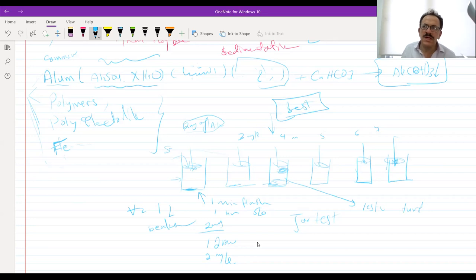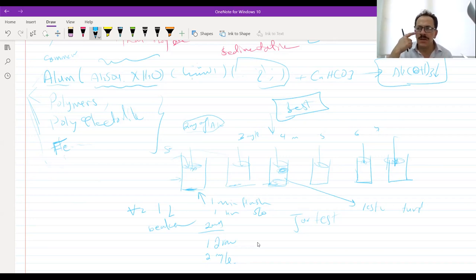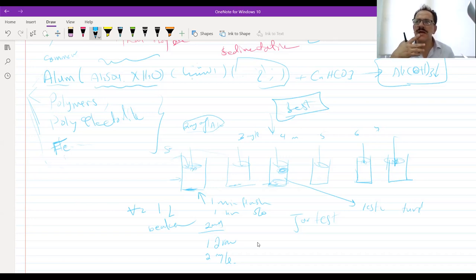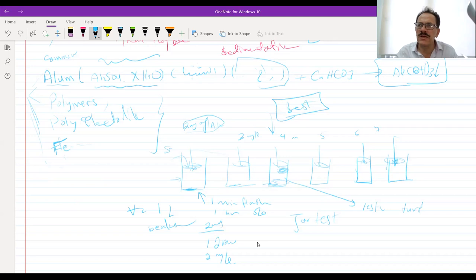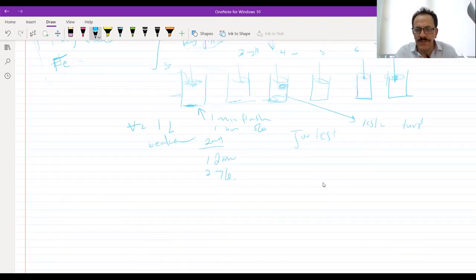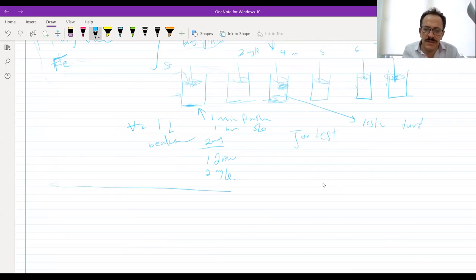The jar test procedure: after adding the doses to the samples, you run all six jars together with a machine that rotates. You mix the chemicals with the sample for one minute rapidly — maybe 400 revolutions per minute. Then, after the one-minute flash mixing, you go for one hour in a slow way, maybe 10 to 20 revolutions per minute.